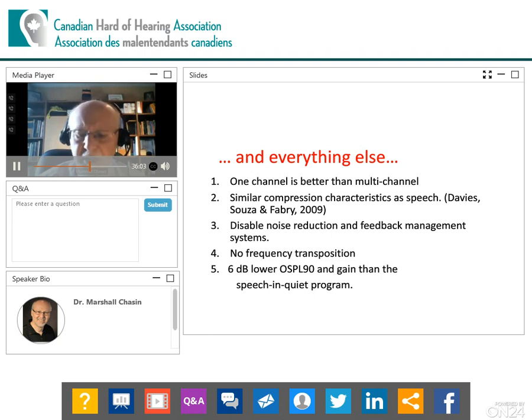Frequency transposition. I haven't really talked about that, but all hearing aids nowadays have what we call frequency transposition or shifting, which takes the sound from the right-hand side of the piano keyboard and moves it to a lower pitch somewhere in the middle or in some extreme cases the left side of the piano keyboard, presumably where you have better hearing. So it takes it from the right-hand side of your hearing test or your audiogram and moves it towards an area where you have better hearing. This has been wonderful for speech. It's improved the intelligibility for speech, but it would destroy music, because when I play a certain note, I'm expecting to hear a harmonic at, let's say, 3,000 hertz, not 2,900 hertz, not 2,800, but exactly 3,000, or else it'll sound flat. And so if you have this frequency transposition working, it will sound odd. So you have to disable the frequency transposition.